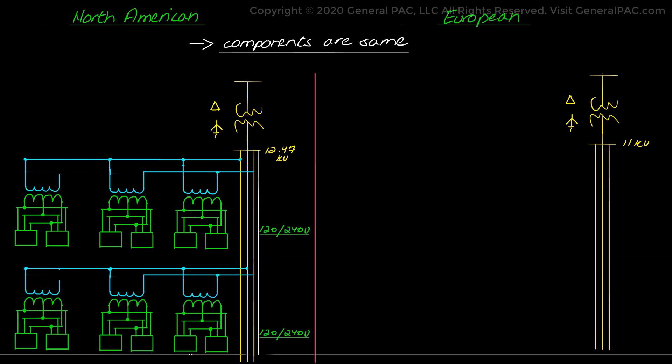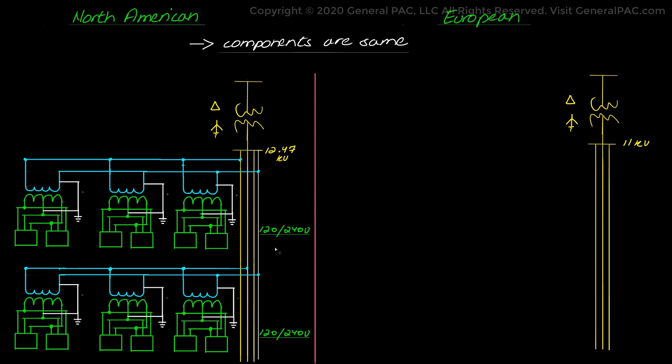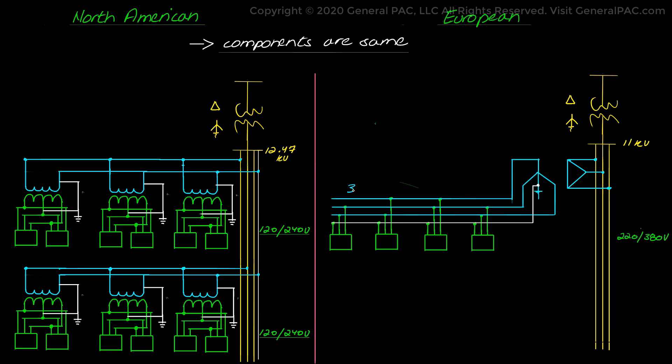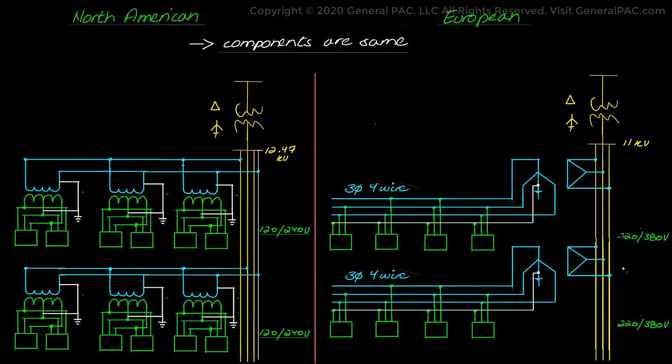The North American layout has three-phase four-wire primary, single-phase laterals, and split-phase distribution transformers. Voltage levels at the service mains is 120/240 volts. The European layout has three-phase three-wire primary, three-phase four-wire secondary, and three-phase distribution transformers. Voltage levels at the service mains are 230/400 volts.